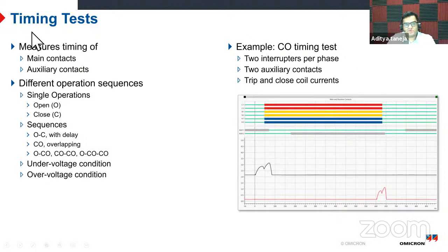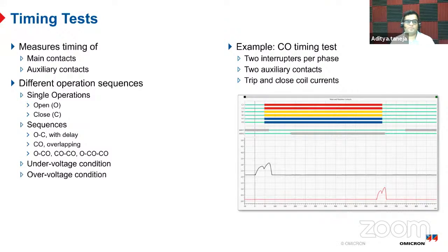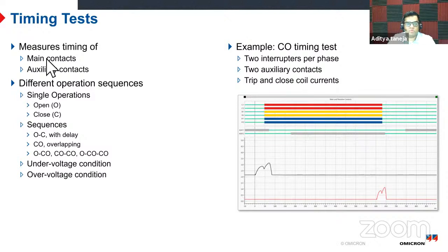So the first test which we talk about is the timing test. This is a very common test, which is done on almost all the breakers in high voltage. What we are trying to do is we give the command to the coil. We simulate the relay command to the coil, trip coil and close coil, and we see when the breaker has operated. So it is kind of an overall test to see the overall performance of the breaker. That is the dynamic performance of the breaker, whether it is working or not, and is it within the time which is the design parameter, or stated by the manufacturer, that this breaker will operate in 2 cycles or a few milliseconds, whatever is the recommended window. It should work within that period.